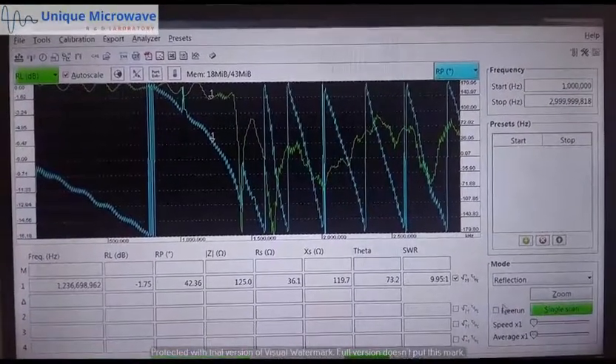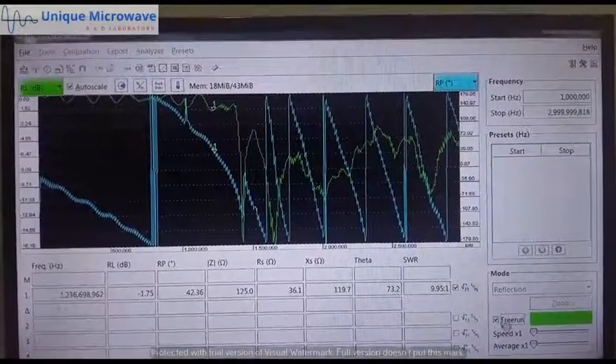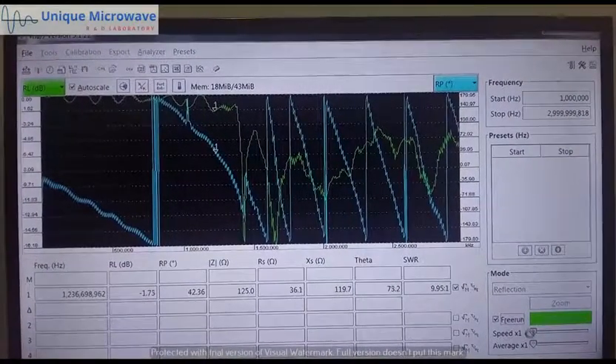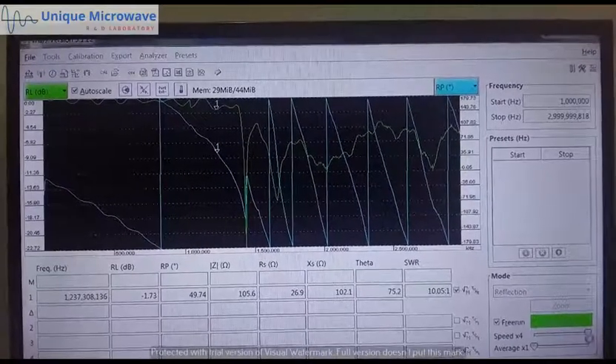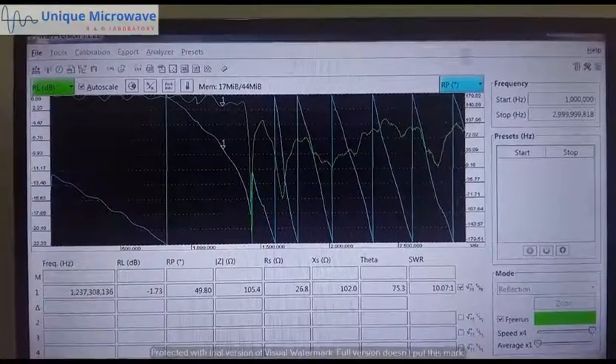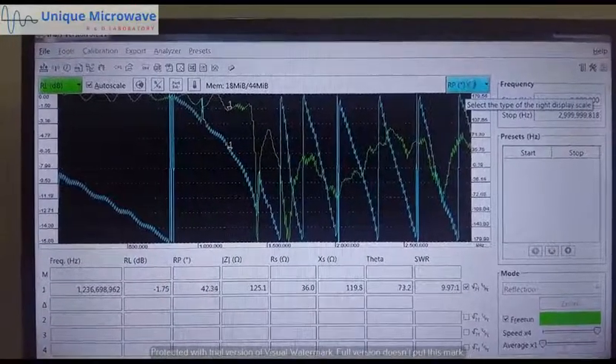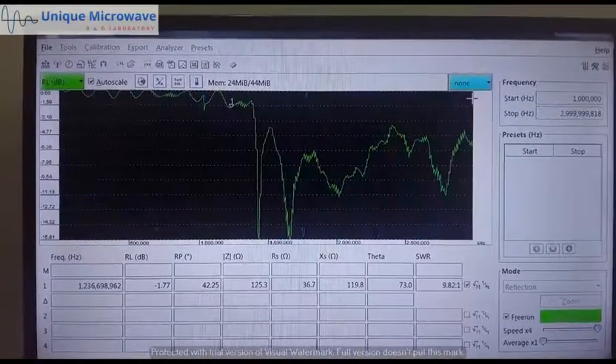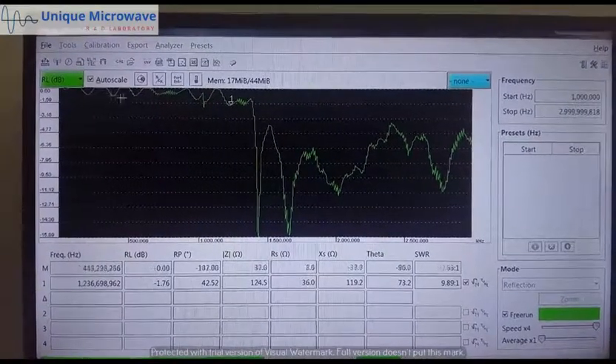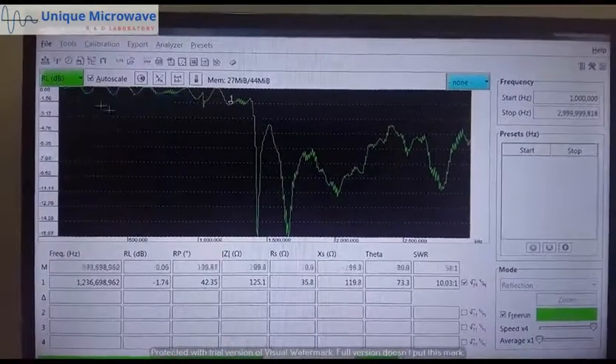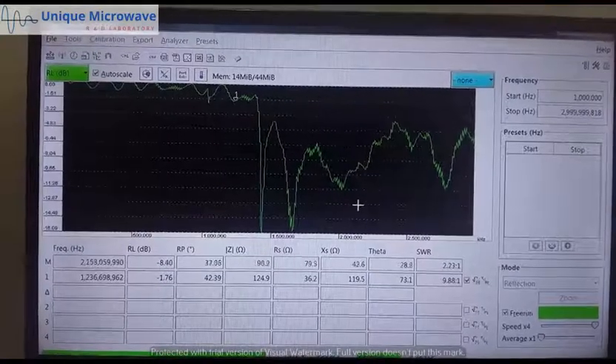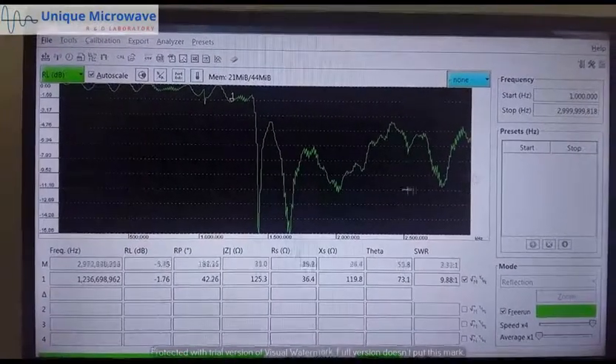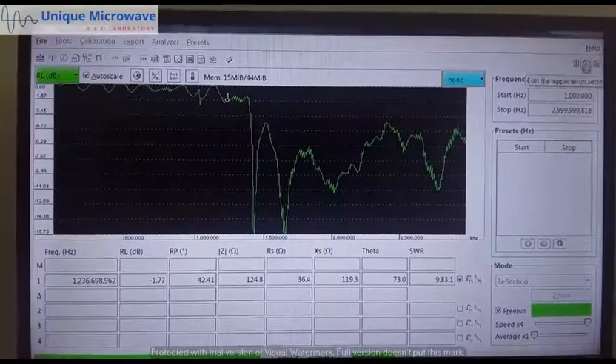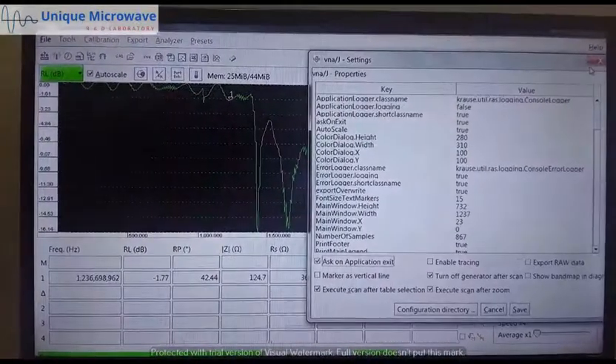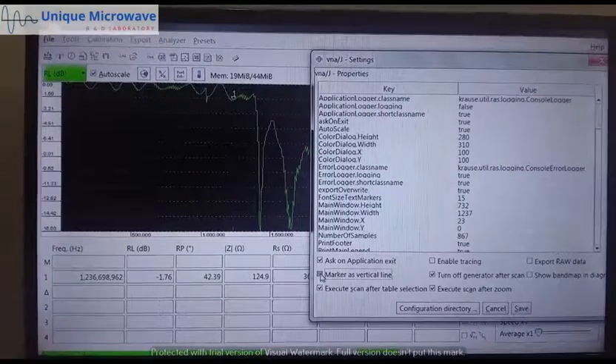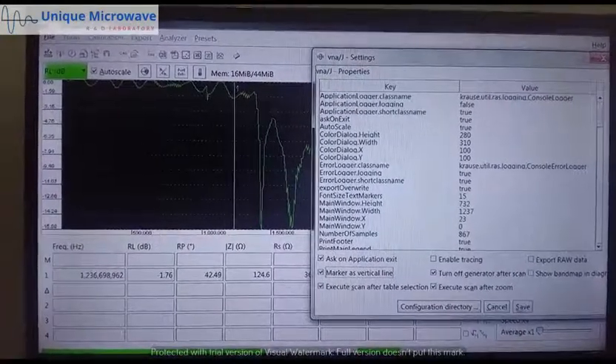First, click Freerun, and then we will need to change the speed to ×4, which is maximum. Then, we will need to disable the phase measurement and change it to none, so that we can only refer to return loss. After that, we will need to put a marker line here. In order to do that, we will need to edit the setting. Click at this icon and tick Marker as Vertical Line. Then we click Save.